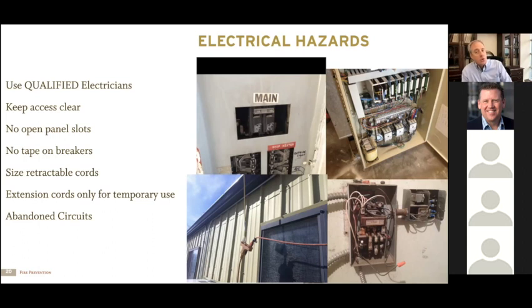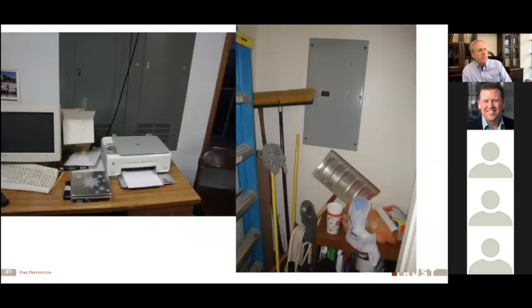And remember, extension cords are for temporary purposes. They're not for permanent wiring. That's another problem we see a lot, like in this picture in the bottom center here, where we've got cords on this building that are basically just attached to the building. And those cords could get damaged either just from UV exposure or from coming into contact with sharp metal surfaces or just over time rubbing over a sharp edge. And then all of a sudden we have an electrocution or a fire hazard. Another problem that we see a lot is the abandoned circuits, and I'll mention that in just a second.